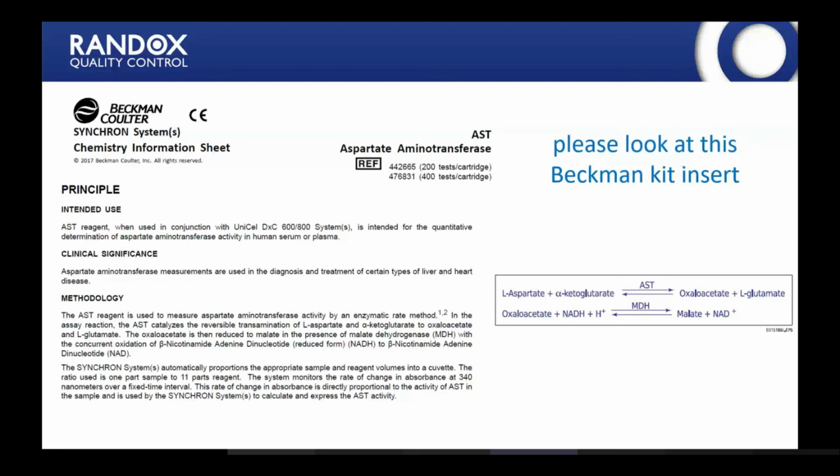It can be down to different calibrations and different standardizations. And because you can have one reagent supplier that provides multiple calibrations and multiple methods, it can be confusing to register correctly. But if you don't, then obviously you're going to be compared to incorrect peer groups, which will be to the detriment of your performance indication.